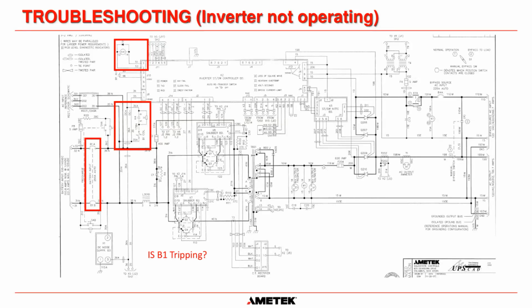Another reason could be B1 tripping. Now, B1 does have a current rating, so it will trip on overcurrent, but it's very, very rare that we see it trip on overcurrent. The most common thing is what we said before, the 105 volts DC for a 60 cell system. All UPS manufacturers have a way to protect the batteries from being completely over discharged. And most battery manufacturers say, once you get down for a lead acid battery to 1.75 volts per cell, you should disconnect the battery to prevent it going any further below that, which could, in theory, if it was left in that state for a long period of time, could cause sulfation of the plates and basically make the battery unrepairable. It won't be able to supply power if it's left in that state for a long time.